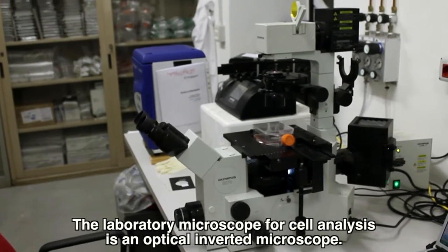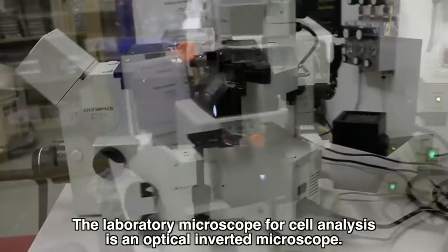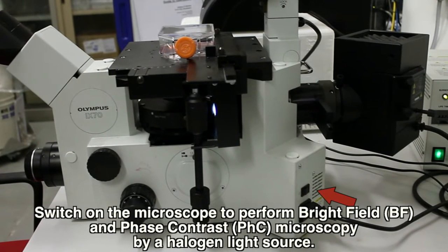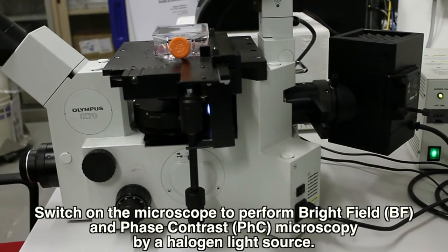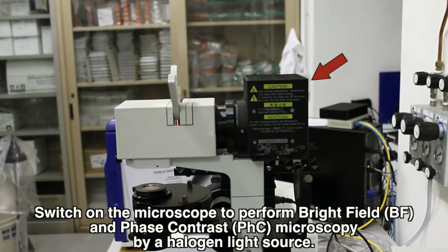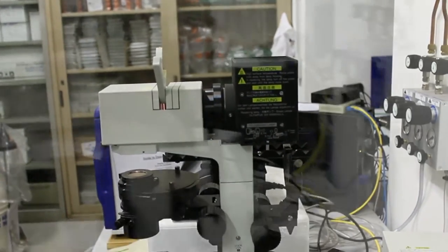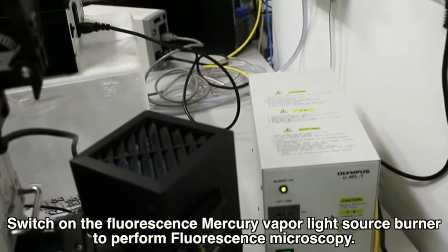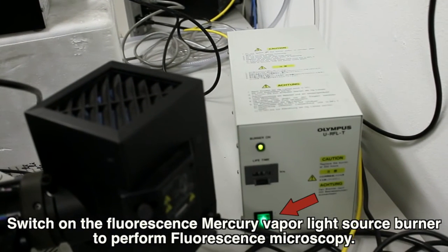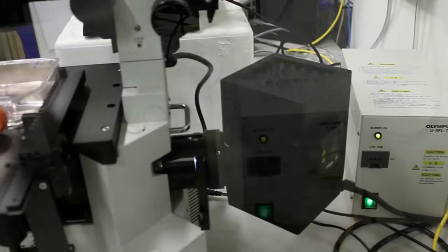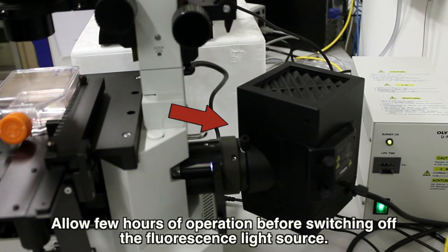The laboratory microscope for cell analysis is an optical inverted microscope. Switch on the microscope to perform bright field and phase contrast microscopy by a halogen light source. Switch on the fluorescence mercury vapor light source burner to perform fluorescence microscopy. Allow a few hours of operation before switching off the fluorescence light source.